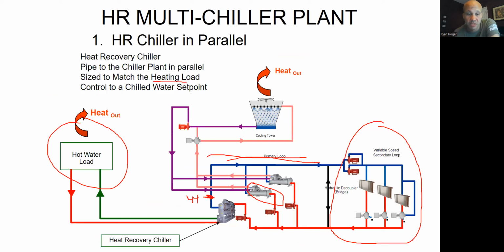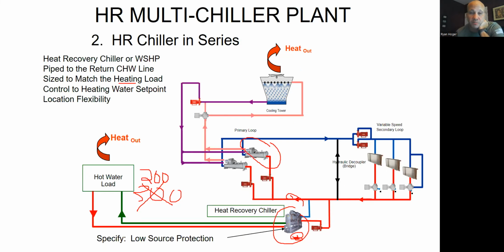And if you notice, these chillers are a little more expensive than a regular chiller up front because you have a little more controls. So I don't want to size it bigger than I need. So typically you size it for the baseline, but it can in fact ramp down. And then if somebody still needs their full amount of cooling, one of the other chillers has to ramp up.